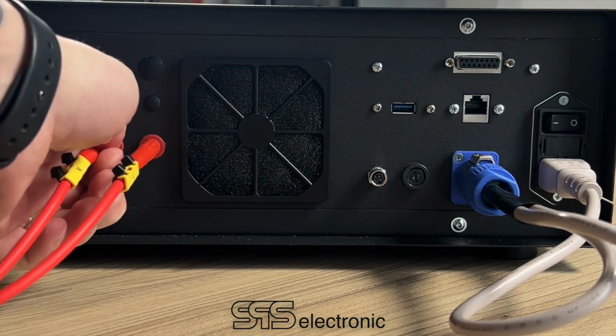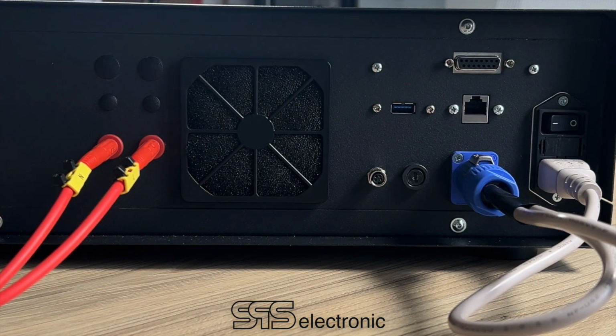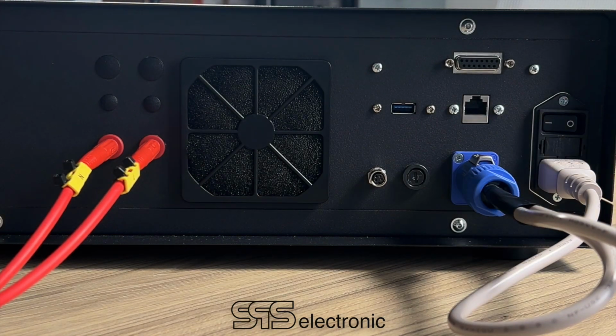No other safety equipment is required, because regarding the norm EN 50191, the tester has a limited power of 350 mJ. That means even though this tester has a 20 mA current, it's still a safety tester.